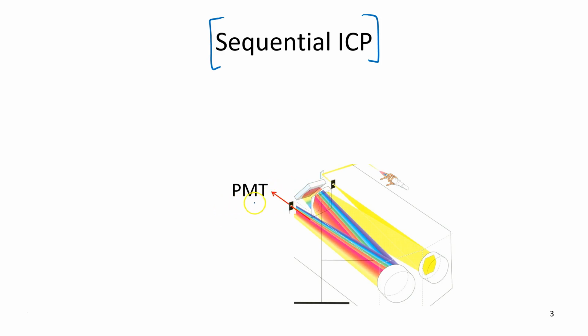You measure that wavelength for about 10 seconds, and then you rotate the grating, and maybe that will allow blue radiation to leave. You measure that for 10 seconds, you rotate the grating a little bit more, and that allows a different wavelength to leave the monochromator, and so on. So I just wanted to emphasize that you don't need a charge coupled device to do so-called simultaneous multi-element analysis. It can be done with a PMT.